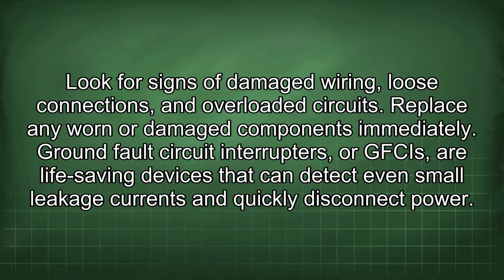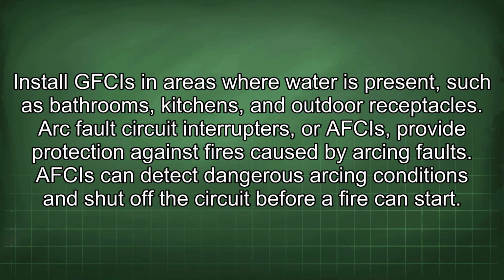Ground fault circuit interrupters, or GFCIs, are life-saving devices that can detect even small leakage currents and quickly disconnect power. Install GFCIs in areas where water is present, such as bathrooms, kitchens, and outdoor receptacles. Arc fault circuit interrupters, or AFCIs, provide protection against fires caused by arcing faults. An AFCI can detect dangerous arcing conditions and shut off the circuit before a fire can start.